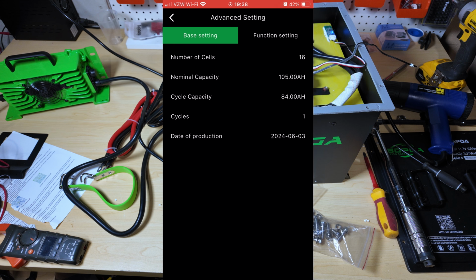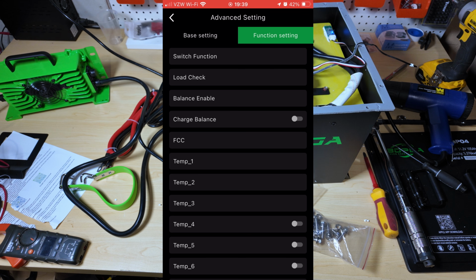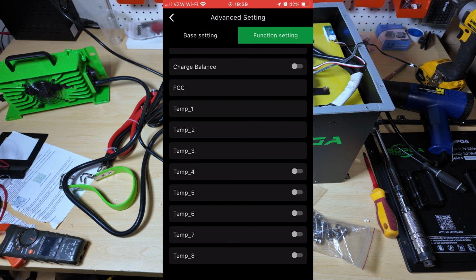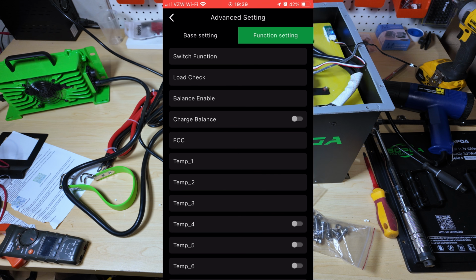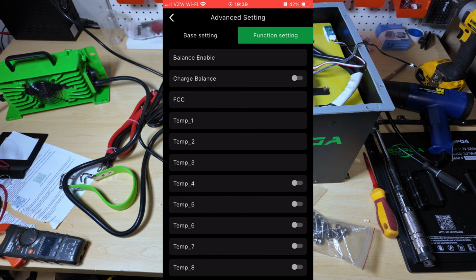Advanced settings, we can see a 16 cell, date of production, June 3rd. I don't know what these function settings are. I know charge balance is an option that only allows balancing to happen while your pack is charging, and you really don't want that, because as soon as you hit an over cell voltage, you stop balancing your pack. And it looks like, I'm guessing, 3 temperature sensors. We know we've got 2, there's probably one in the BMS, so 3 temperature sensors.